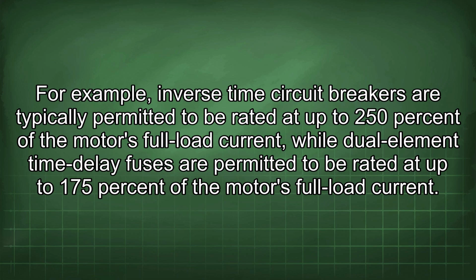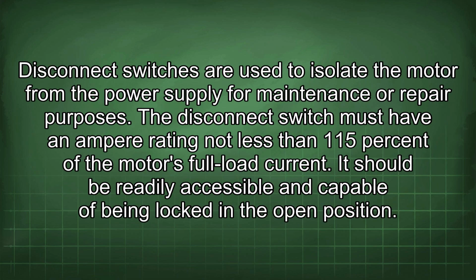full load current. Disconnect switches are used to isolate the motor from the power supply for maintenance or repair purposes. The disconnect switch must have an ampere rating not less than 115% of the motor's full load current. It should be readily accessible and capable of being locked in the open position.